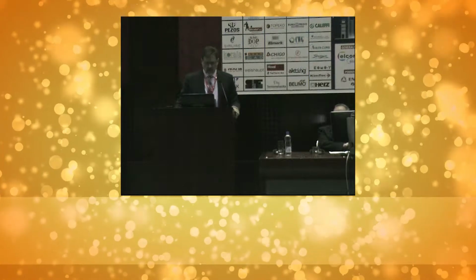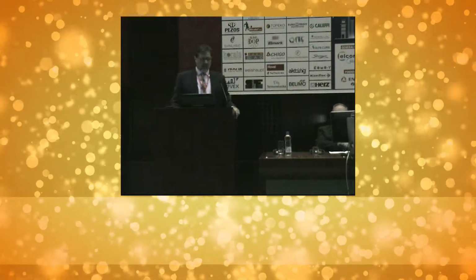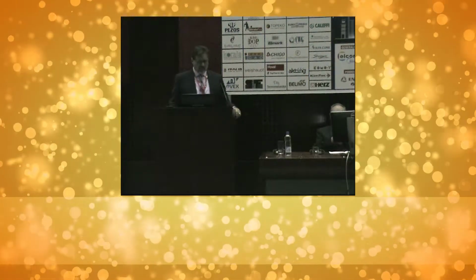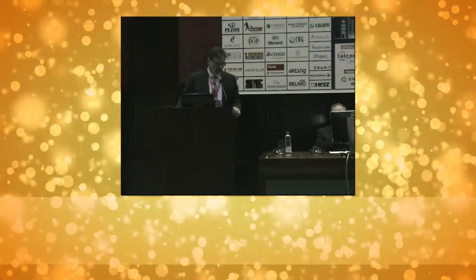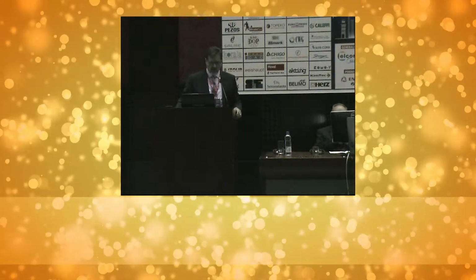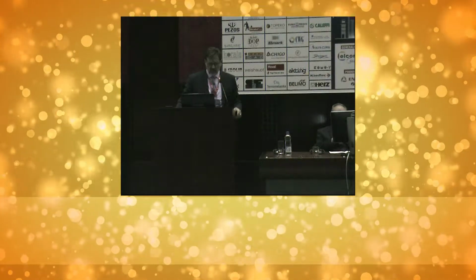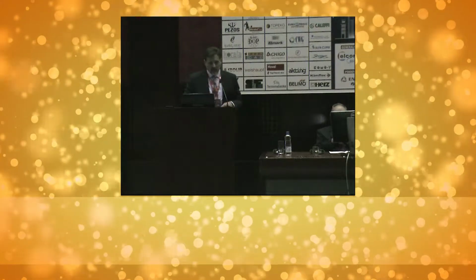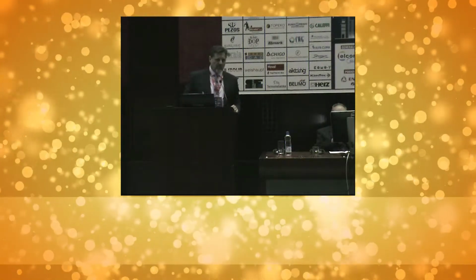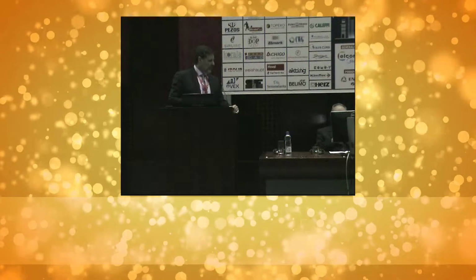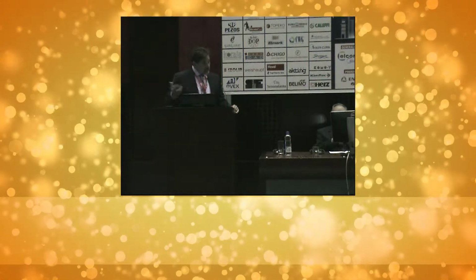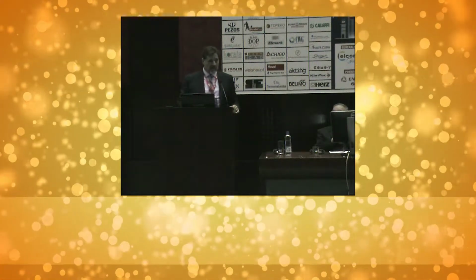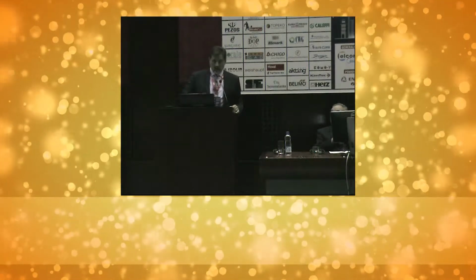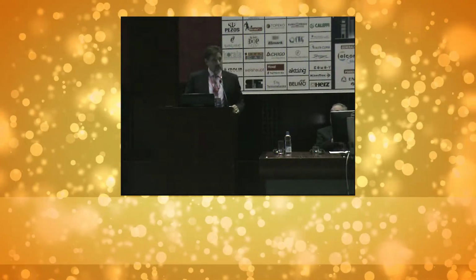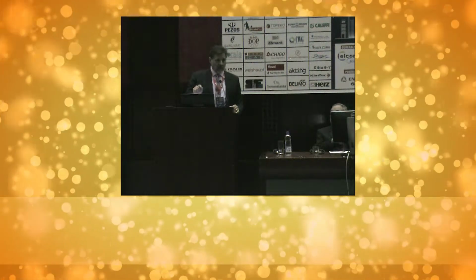Number 4 comes close to our topic, which is the minimum airflow. How do we set the minimum airflow, and why is it really important? Remember, ASHRAE 62.1 now dictates that we're supposed to always have proper ventilation for the people when they are in the room, and we say, hey, listen, there are no people in unoccupied mode. So what do we do? Well, this is the key.